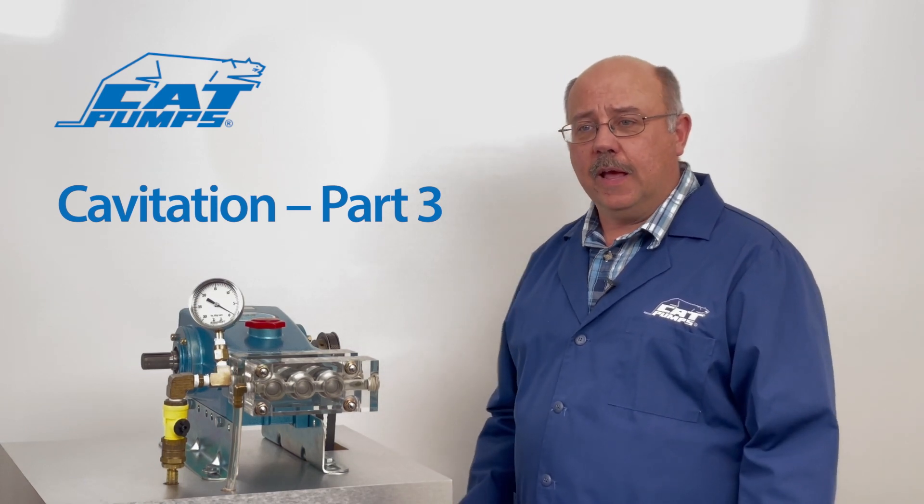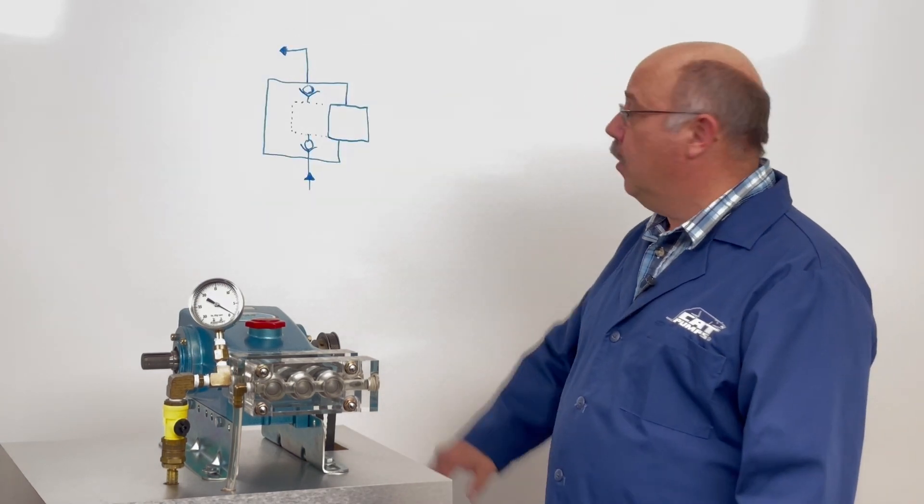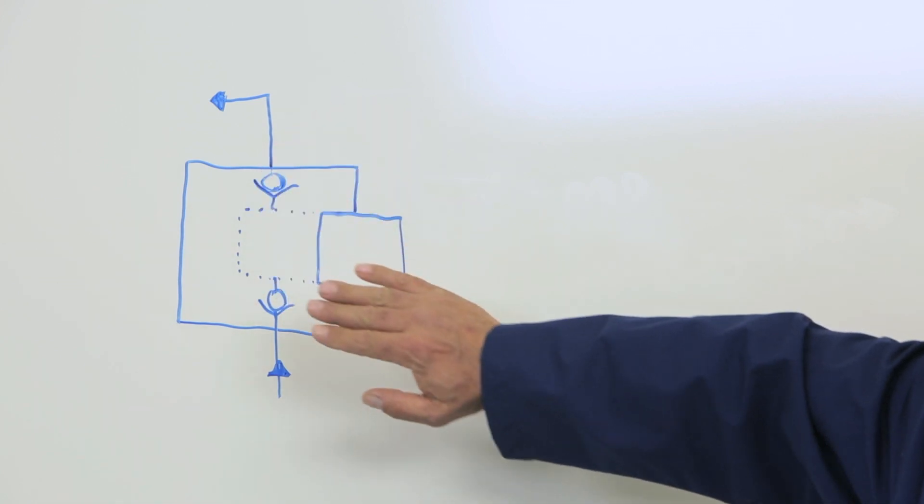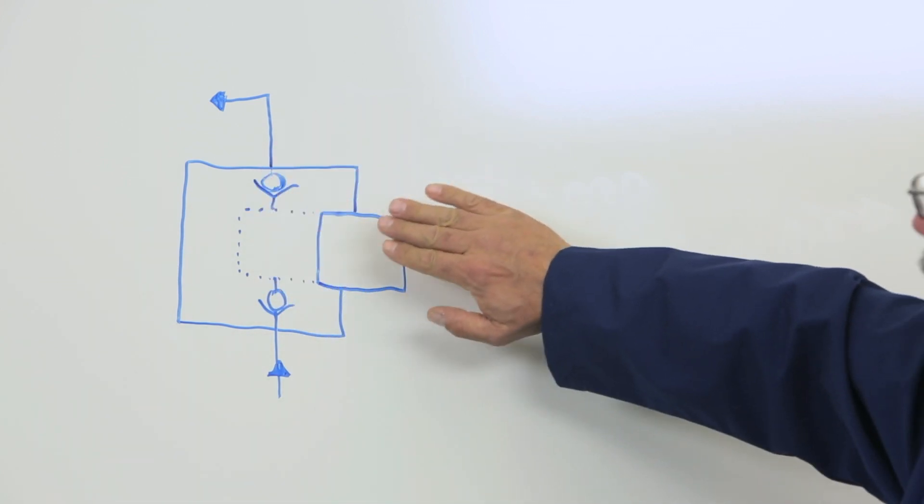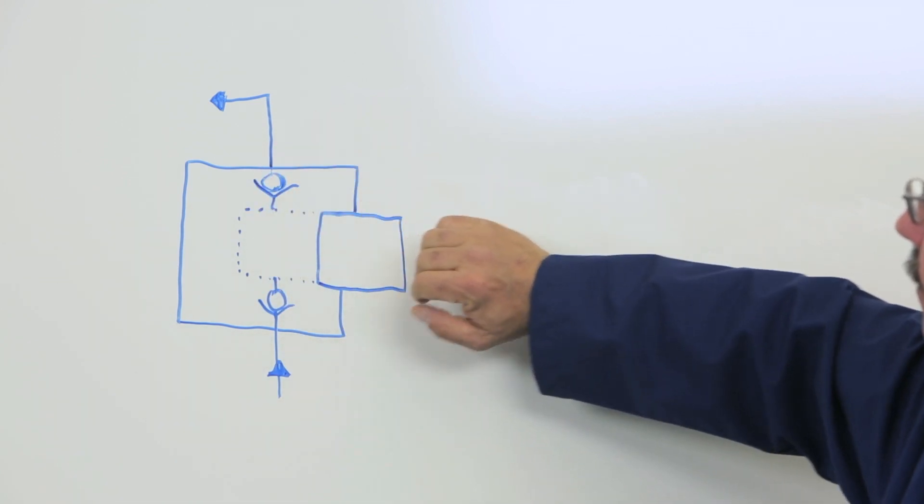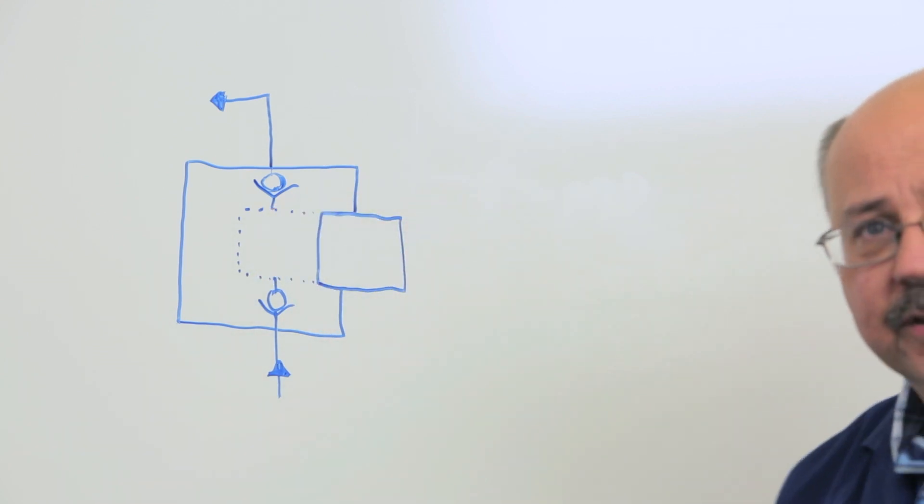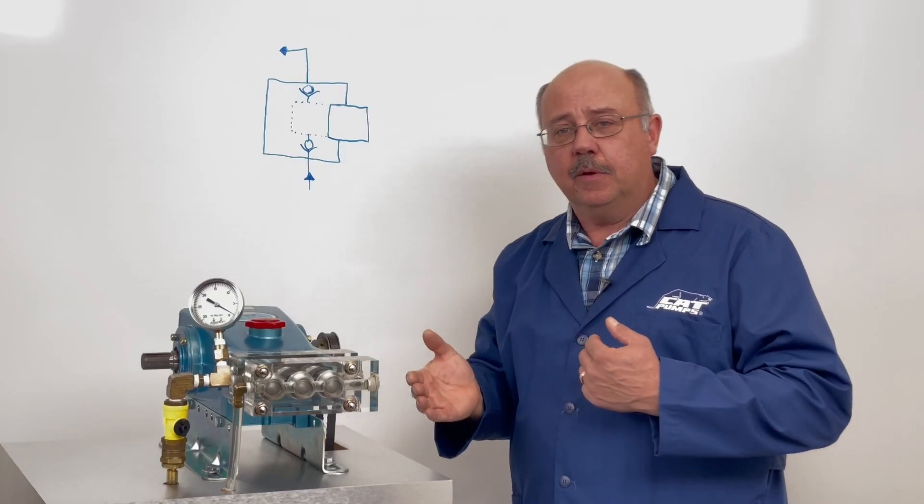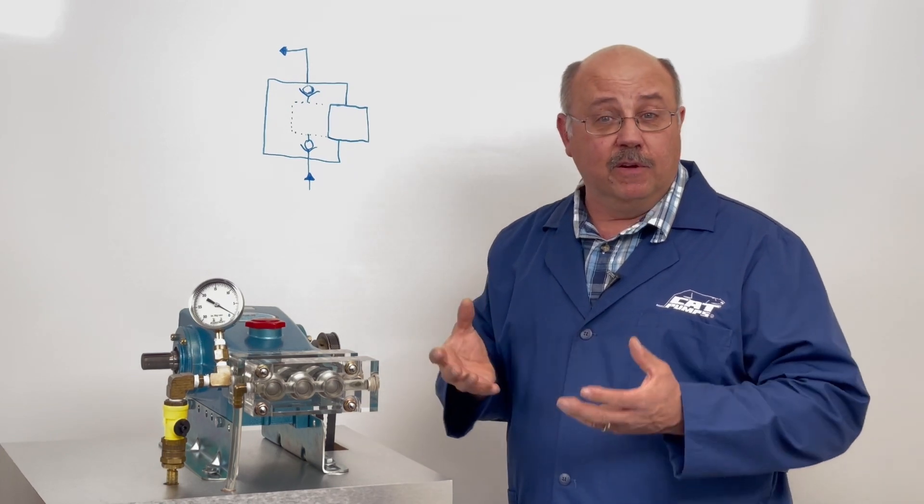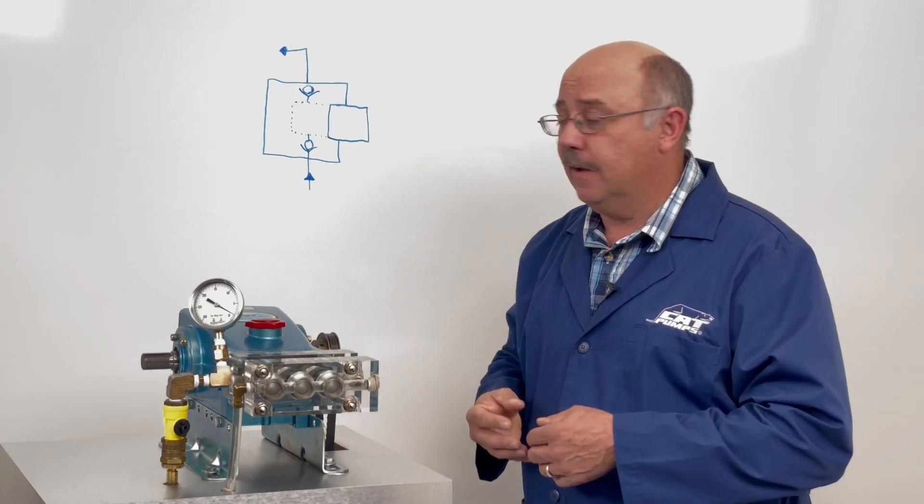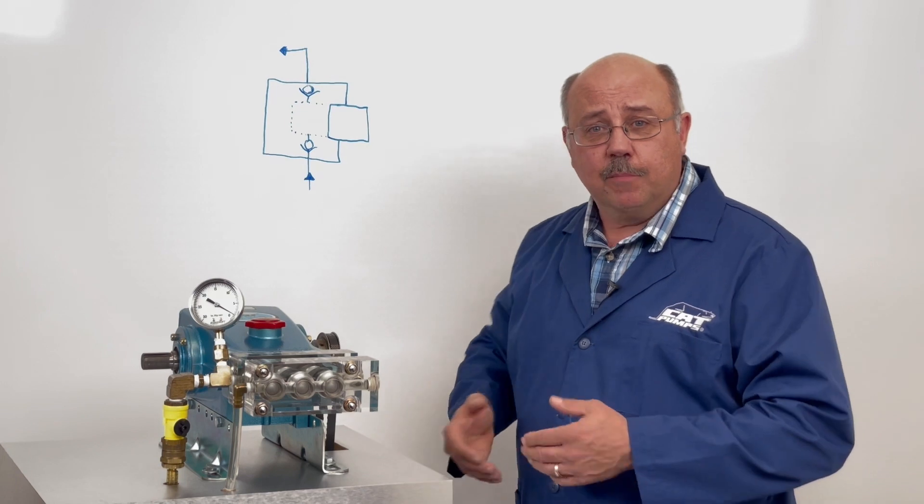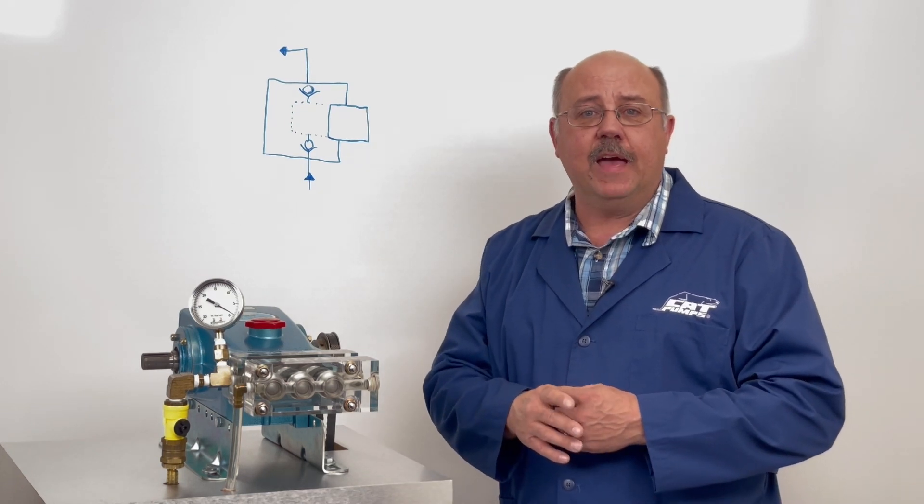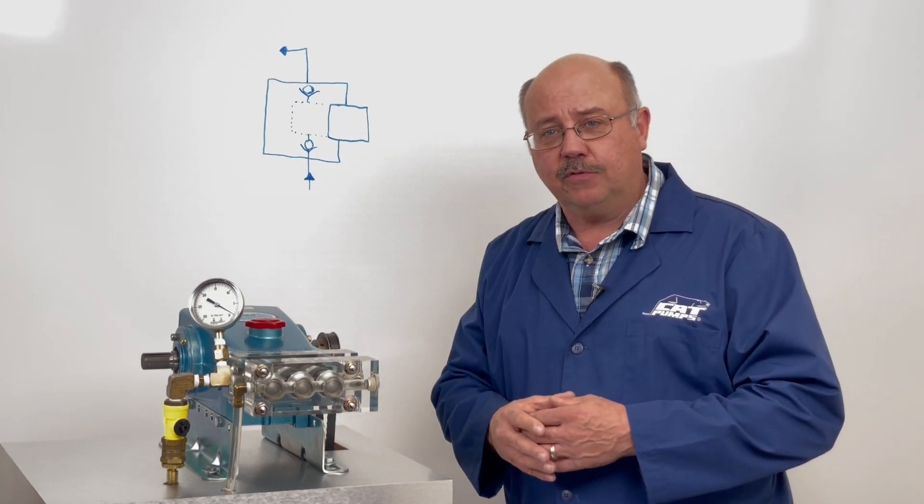So what we're going to look at is, as we did in part one, we had a pumping chamber that we'd drawn on the whiteboard, and it had a plunger, inlet valve, discharge valve, and it showed as the plunger went back and forth, that on the reverse direction, it had to fill that pumping chamber with water, and if we couldn't fill the chamber, it would turn a little bit of that liquid into a gas phase.